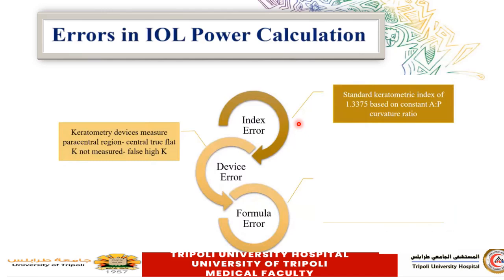So we need to use another machine, the topography. The same problem exists in Placido disc-based topography: the very central point of the cornea cannot be measured but is extrapolated by the machine, because that location contains the camera of the machine, which measures the mirrors or rings of light on the cornea. They measure the adjacent areas, and the very central point of the cornea is extrapolated. So it doesn't give a real calculation of the central 1 to 1.5 millimeter zone of the cornea.